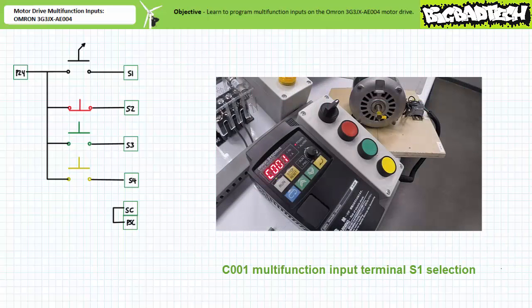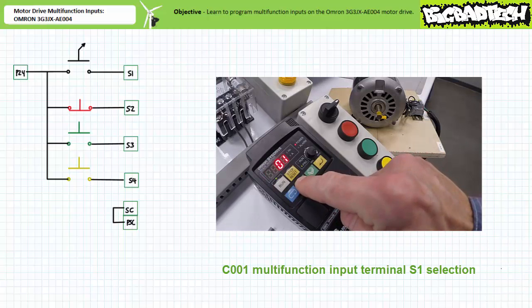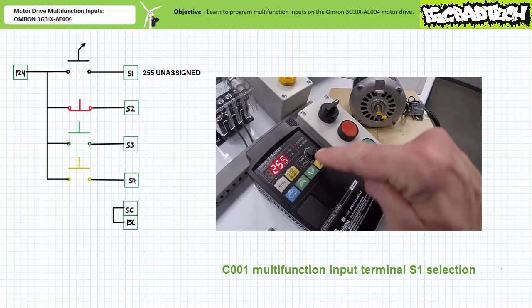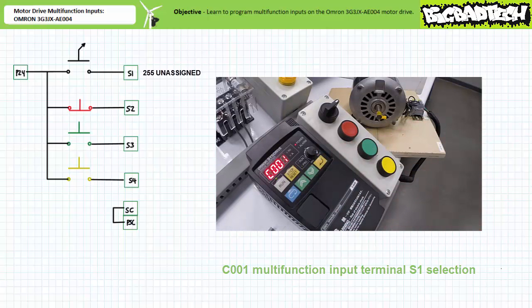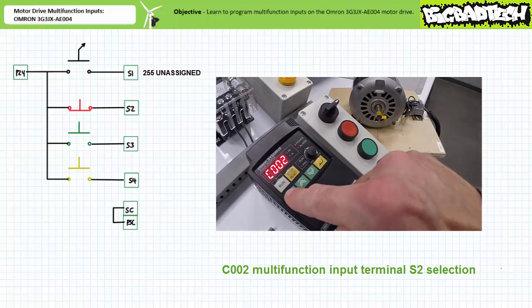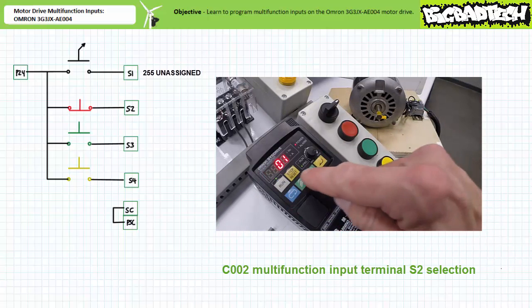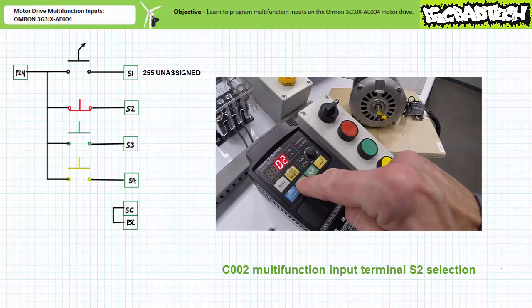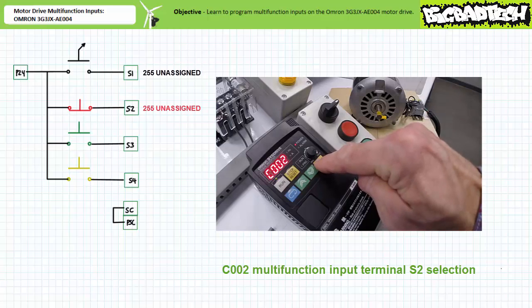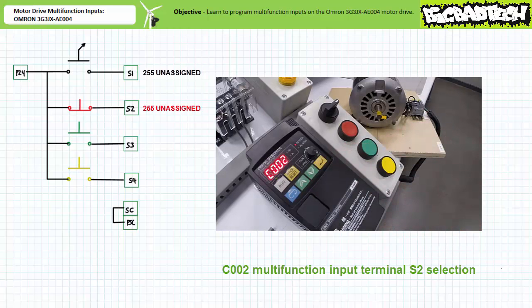Navigate to communication parameter C001, multi-function input one selection. Press mode. As anticipated, it is in the default state of 00, forward. Increment this to 255, unassigned, and press enter to save it. Navigate to communication parameter C002, multi-function input two selection. Press mode. As anticipated, it is in the default state of 01, reverse. Increment this to 255, unassigned, and press enter to save it.